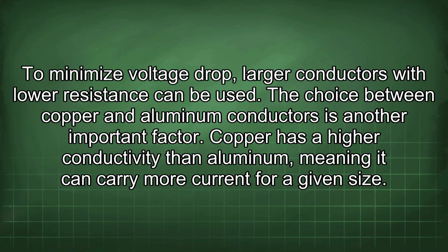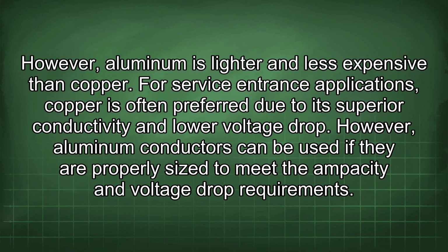The choice between copper and aluminum conductors is another important factor. Copper has a higher conductivity than aluminum, meaning it can carry more current for a given size. However, aluminum is lighter and less expensive than copper. For service entrance applications, copper is often preferred due to its superior conductivity and lower voltage drop. However, aluminum conductors can be used if they are properly sized to meet the ampacity and voltage drop requirements.